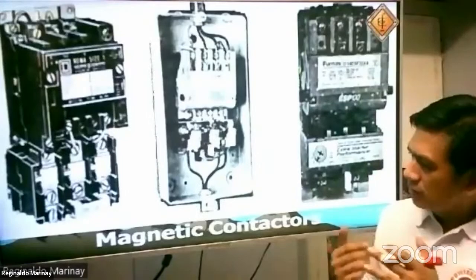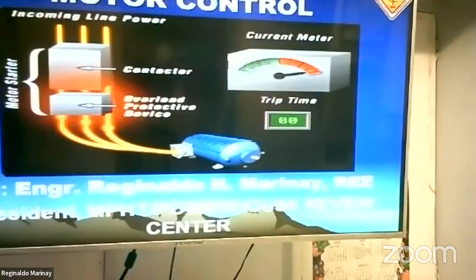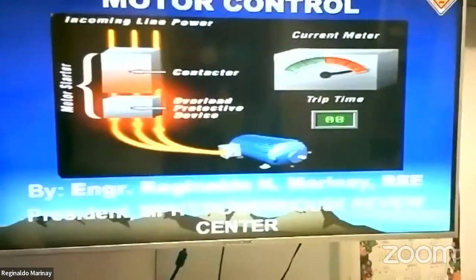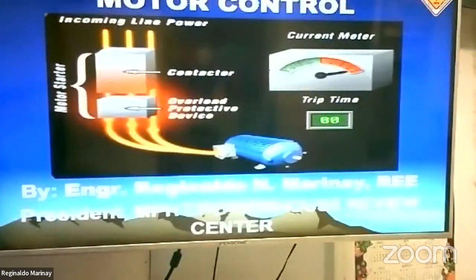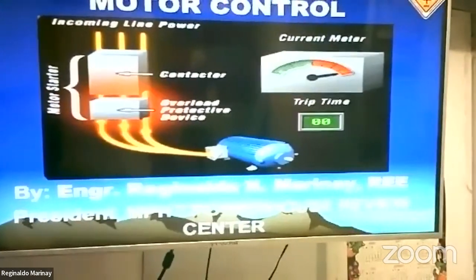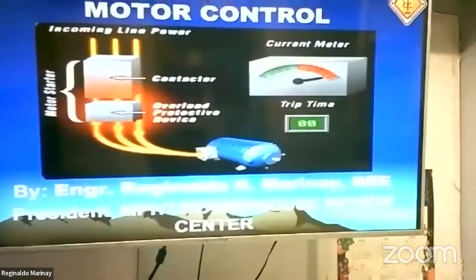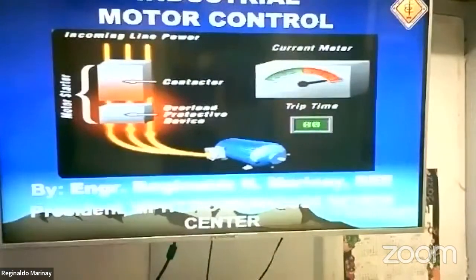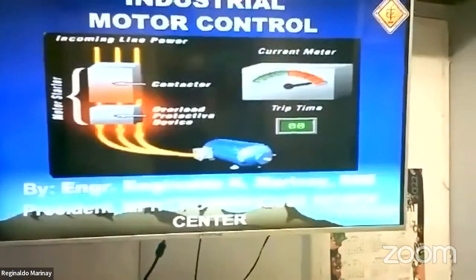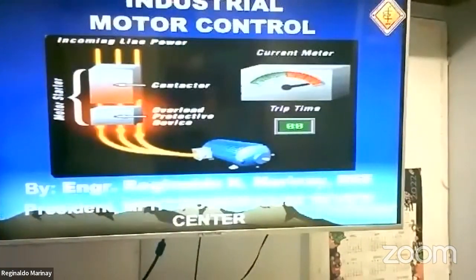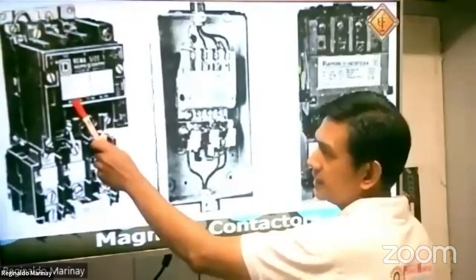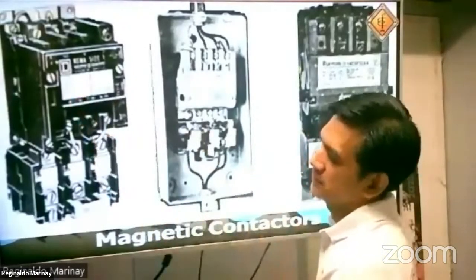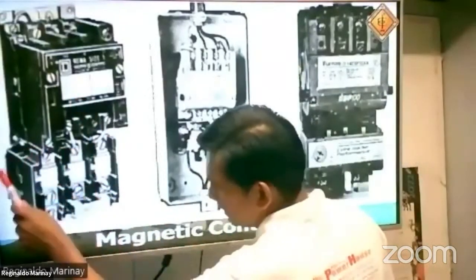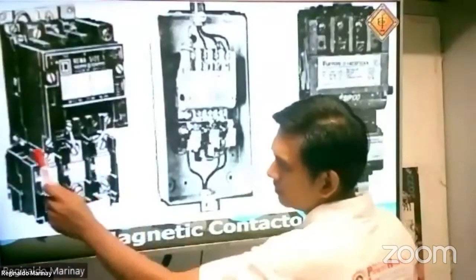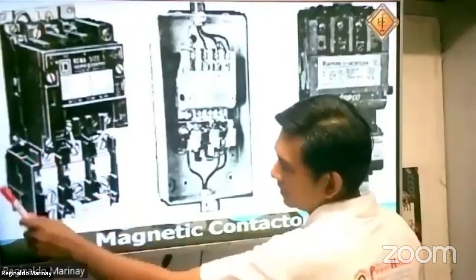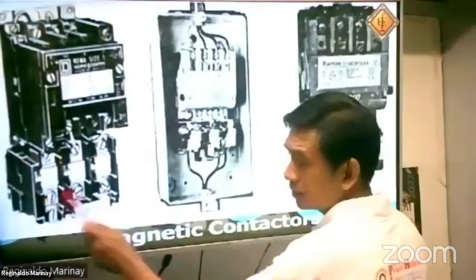Okay, so this is a magnetic contactor. As you see here, this is our magnetic contactor, and this is our overload relay. You see this one. So our magnetic contactor is simply a switch, an electrically operated switch. This overload relay is a type of motor protection that will protect against overload condition.